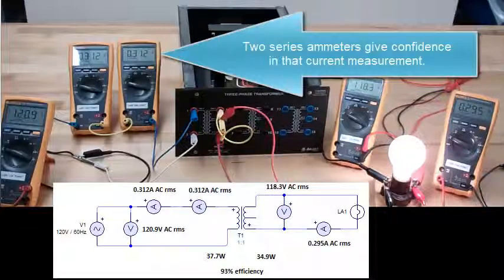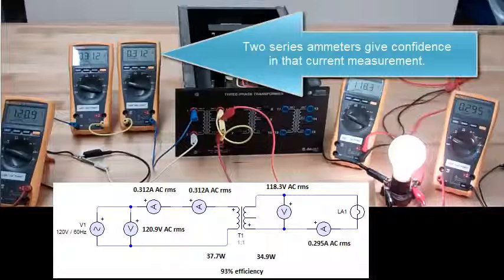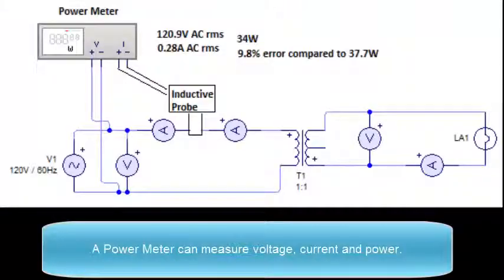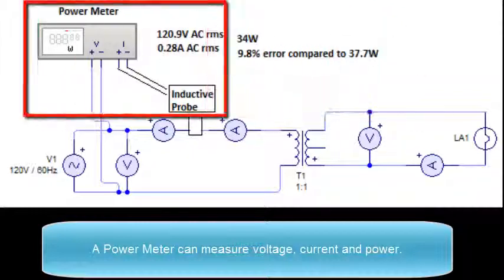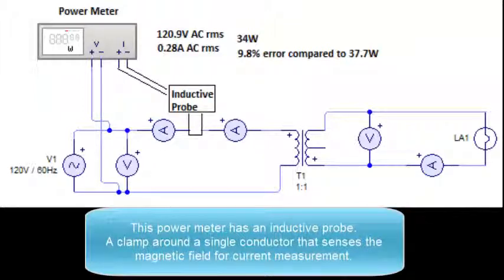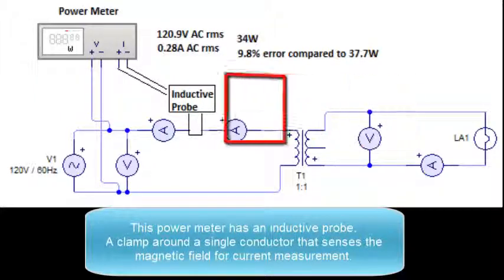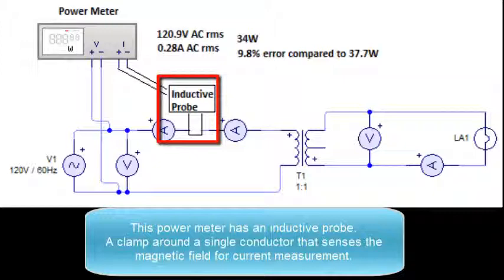The two series ammeters give confidence in the current measurement. A power meter can also measure voltage, current, and power. This power meter has an inductive probe. That's a clamp around a single conductor that senses the magnetic field for current measurement.